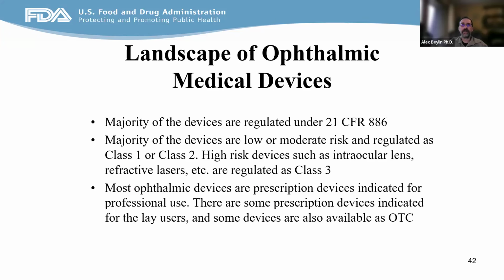Most ophthalmic devices are regulated under Title 21 of the Code of Federal Regulation, Part 886. However, some are regulated under different parts of the CFR, like neurology or radiology. Most devices are low or moderate risk and regulated as Class 1 or Class 2. However, some high-risk devices, such as intraocular lenses or refractive lasers, are regulated as Class 3. Most ophthalmic devices are prescription devices indicated for professional use. However, some prescription devices are indicated for lay users, such as home-use tonometers or contact lenses. Some ophthalmic devices are also available over-the-counter, for example reading glasses and digital visual acuity charts.